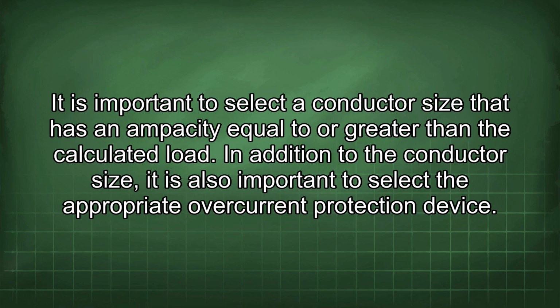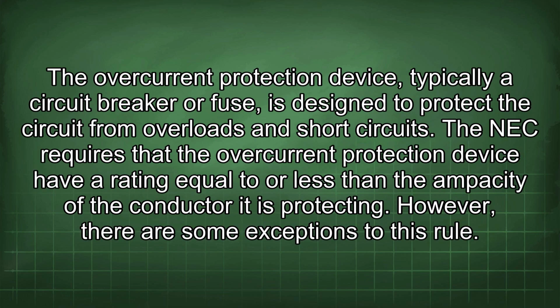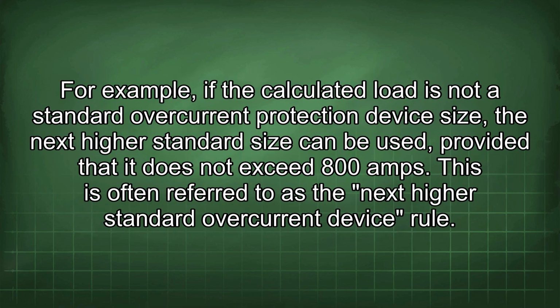In addition to the conductor size, it is also important to select the appropriate overcurrent protection device. The overcurrent protection device, typically a circuit breaker or fuse, is designed to protect the circuit from overloads and short circuits. The NEC requires that the overcurrent protection device have a rating equal to or less than the ampacity of the conductor it is protecting. However, there are some exceptions to this rule. For example, if the calculated load is not a standard overcurrent protection device size, the next higher standard size can be used, provided that it does not exceed 800 amps. This is often referred to as the next higher standard overcurrent device rule.